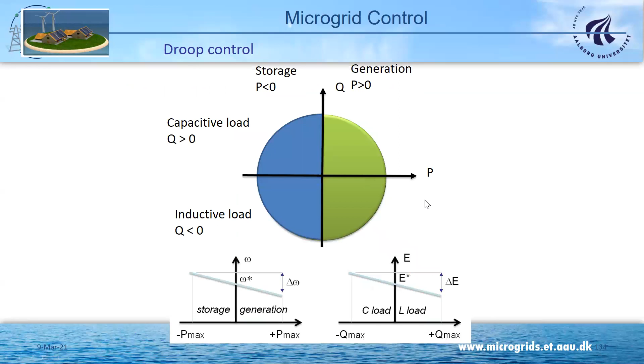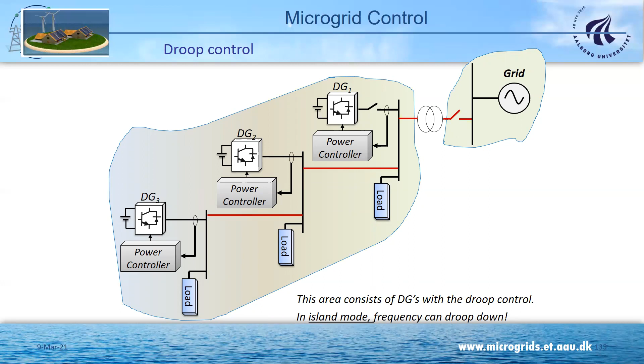You can export these ideas to systems with generation and storage as well. This means that when a microgrid is suddenly disconnected from the main grid, its frequency depends on the total amount of load: if demand exceeds generation, frequency goes down; if generation exceeds consumption, frequency goes up. This is the principle we try to emulate in microgrids.